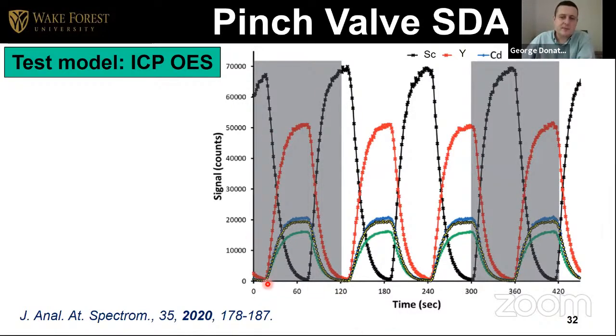But you can see the signal of the analytes going up first with the first internal standard, and the signal from the second internal standard going down, and then it goes up. And this is the cycle through the measurement. And with that, you can have many, many points to do the calibration curve.